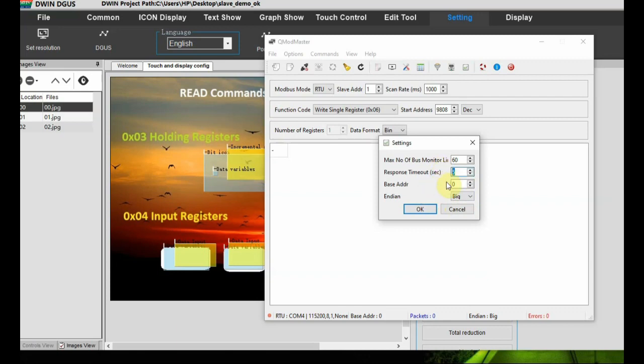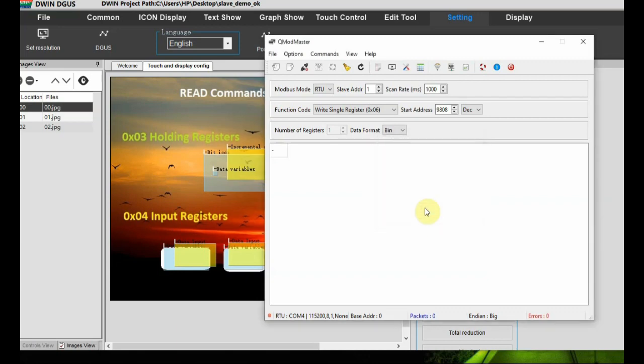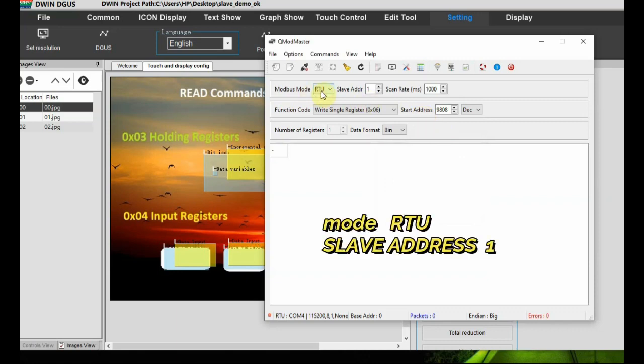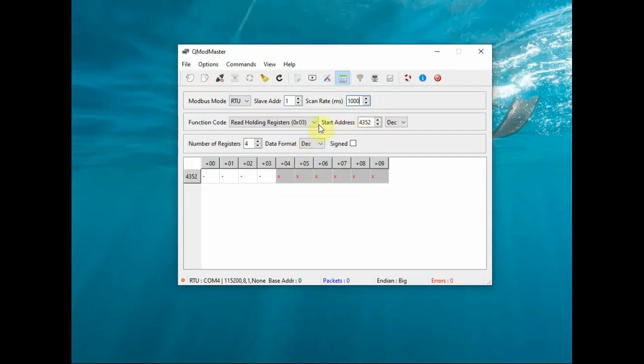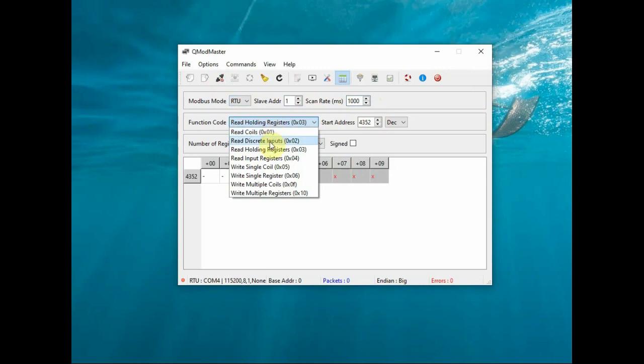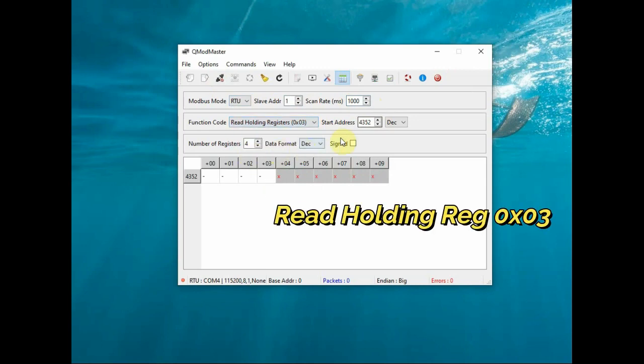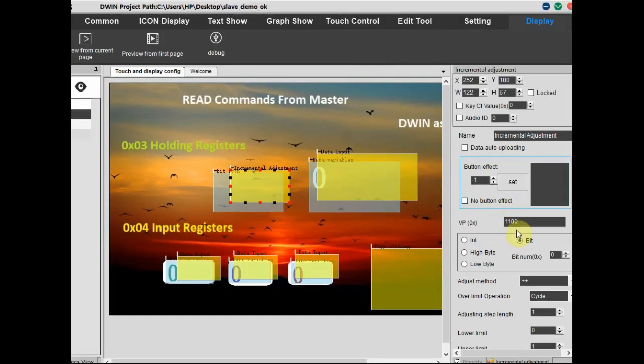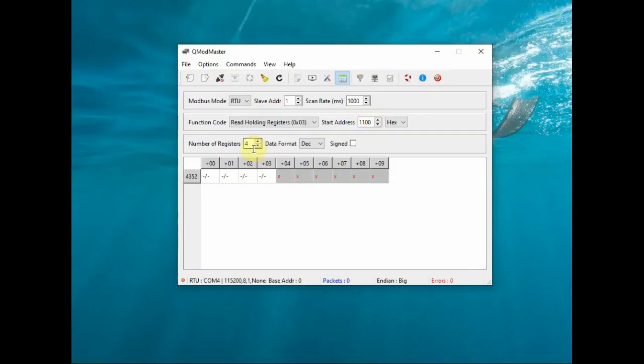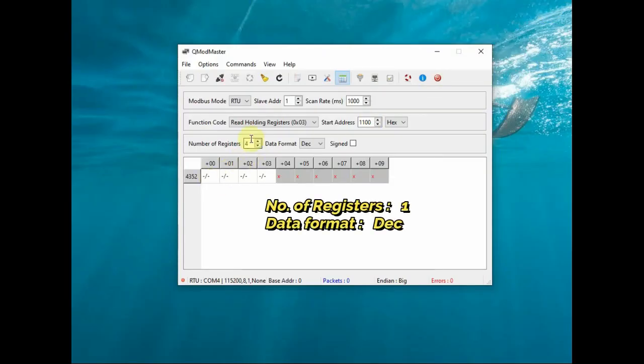The base address must be zero - this is very important. Select OK. The Modbus mode must be RTU and the slave address is 1, as in the OS file we are using slave address 1. Now click on Connect. Before that, select the function code - let us select read holding registers 0x03, and the start address is the VP address.